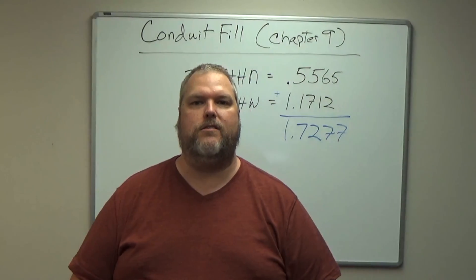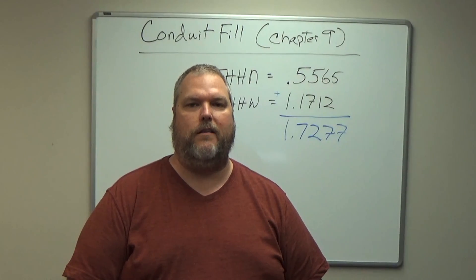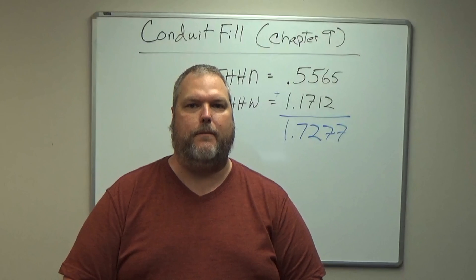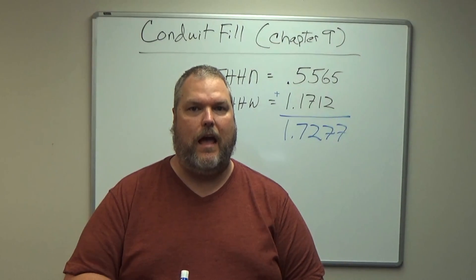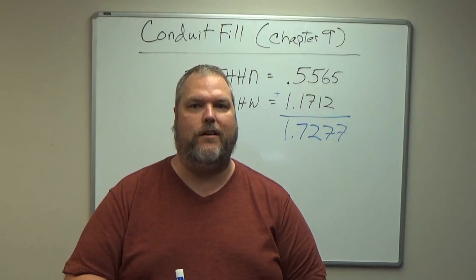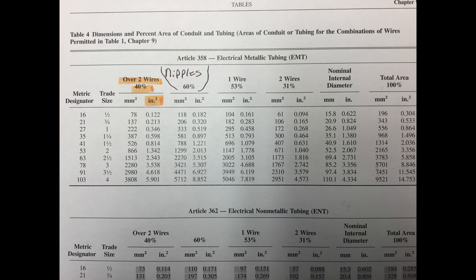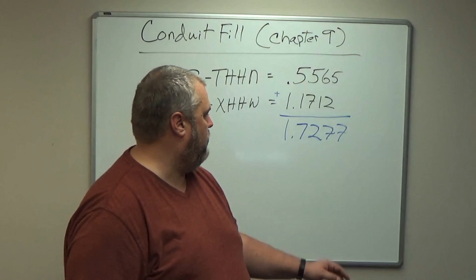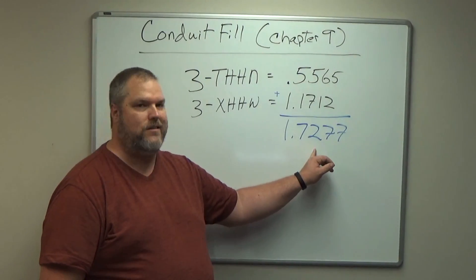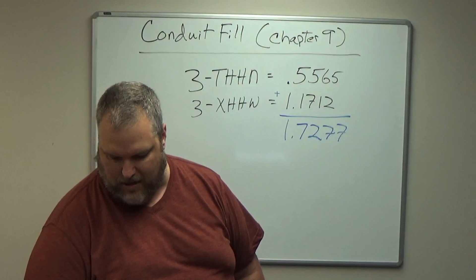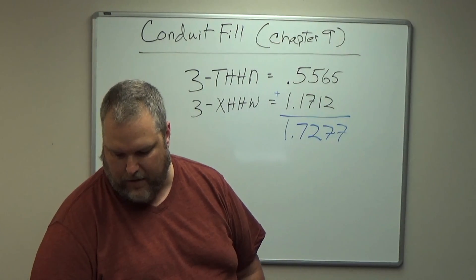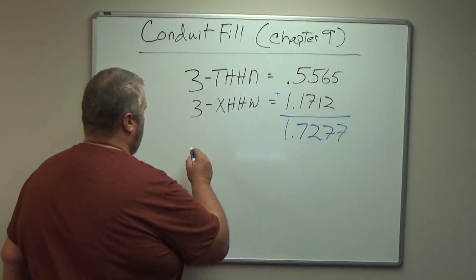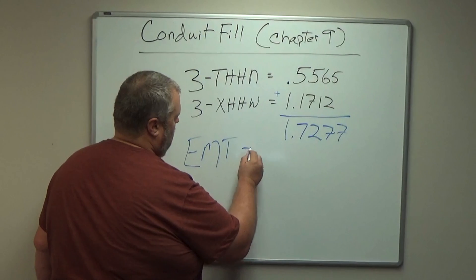Now we have to go back to chapter 9, table 4, look under EMT, find our area at 40%, and run down the square-inch column until we find the right size. We see 1.342 — but 1.342 is smaller than 1.7277, so we have to go to the next available size, which is 2.343, which corresponds to EMT two-and-a-half inch conduit.